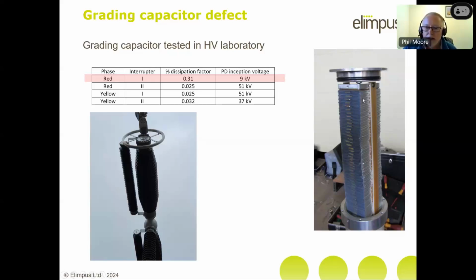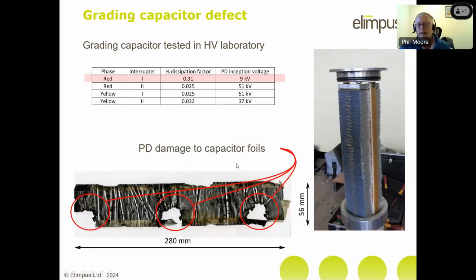And so what they were able to do with this particular one, the one that had failed, was that they took it apart, and the first thing that they noticed when they took it apart is that the oil that came out of the grading capacitor was black. It wasn't mineral oil coloured. It was very, very badly degraded. And when they unfolded quite a lot of these individual units, they discovered this sort of effect. It was almost as though somebody had taken a rifle and shot it along the length of the capacitor. It wasn't actually all the way through it, but it was through quite a large chunk of it.